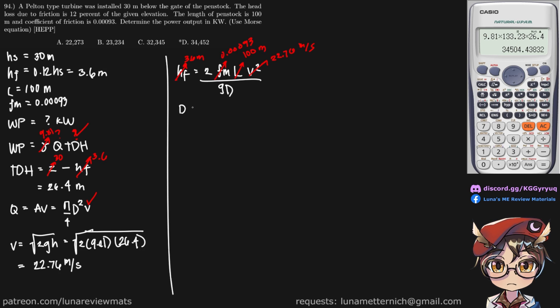We can use Shift-Solve in order to find our penstock diameter. And if you Shift-Solve that, it should return a value of 2.73 meters.